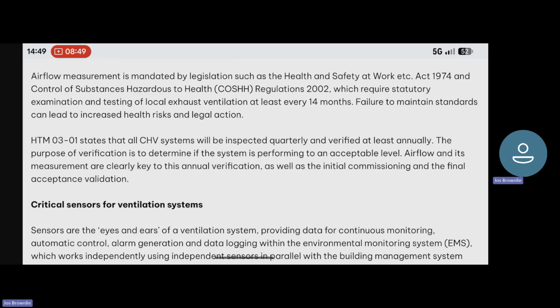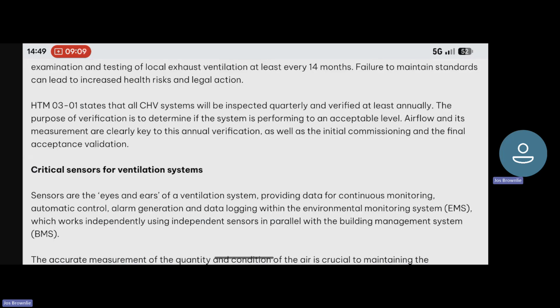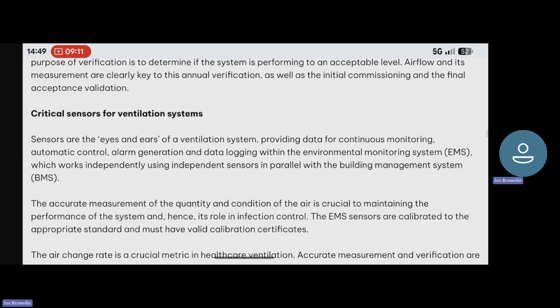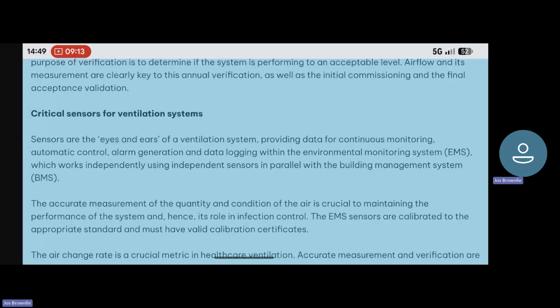HTM 03-01 states that all CHV systems will be inspected quarterly and verified at least annually. The purpose of verification is to determine if the system is performing to an acceptable level. Airflow and its measurements are clearly key to this annual verification, as well as the initial commissioning and the final acceptance validation. Critical sensors for ventilation systems.